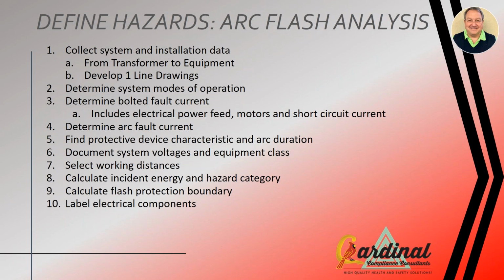We're going to start at your incoming power feed to your transformers, all the way down to your equipment. They want you to develop one-line drawings, because it's a great vehicle for conveying what the different levels of arc flash are within your system and the different voltages. So it's a great graphical representation of what you've got. They want you to determine, how does this place run?